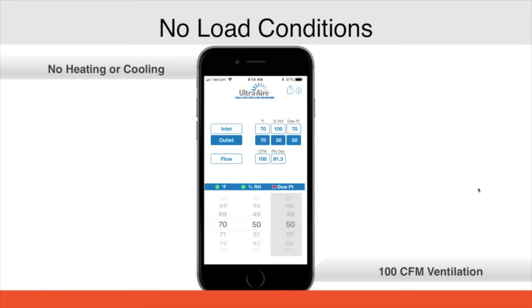And then we go into no load conditions. So this is our 70 degrees and 50% relative humidity, not running any AC, most likely. 100 CFM of outdoor air. I'm going to need 91 pints of moisture removal a day. And these are just based on ventilation. If we also need to calculate the occupants in the home, a family of 4 would be about 2 pints or pounds of moisture an hour as well. So we would need to add that load onto this as well.